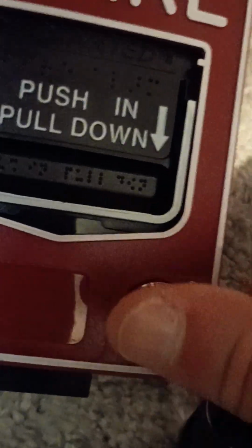There's a knob in the back. Once it's activated, to reset it you insert the key, open the door up, flip it, and there's an LED inside that turns red once the alarm is triggered. The only way the LED goes off is if you go to the panel or annunciator and reset the whole system.